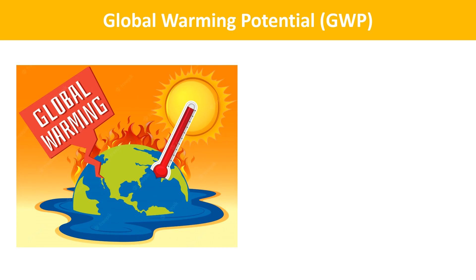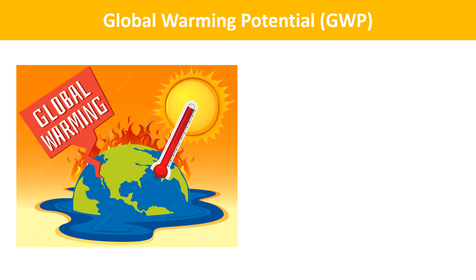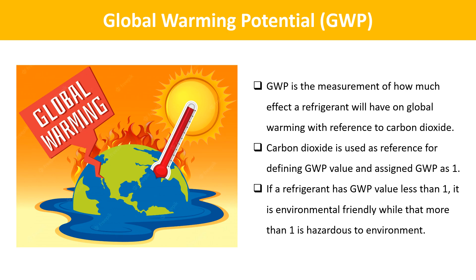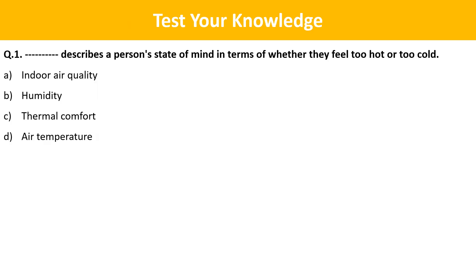The next term is Global Warming Potential. Refrigerants used in an AC unit contribute to global warming to a more or less extent. GWP is the measurement of how much effect a refrigerant will have on global warming with reference to carbon dioxide. Carbon dioxide is used as the reference for defining GWP and is assigned a GWP value of 1. If a refrigerant has a GWP value less than 1, it is environmentally friendly, while a value more than 1 is hazardous to the environment.